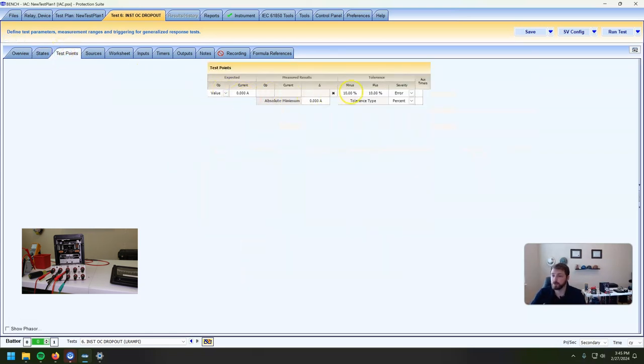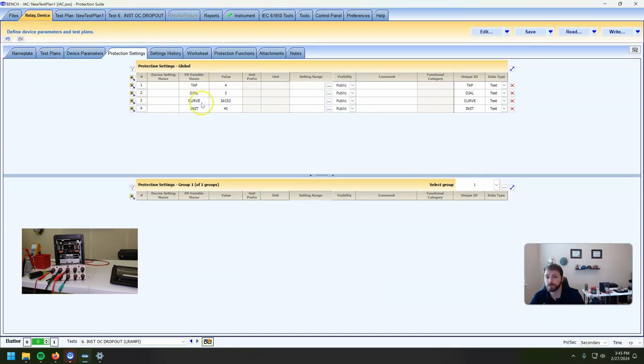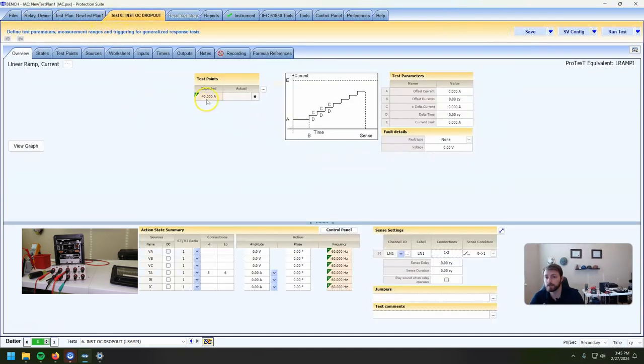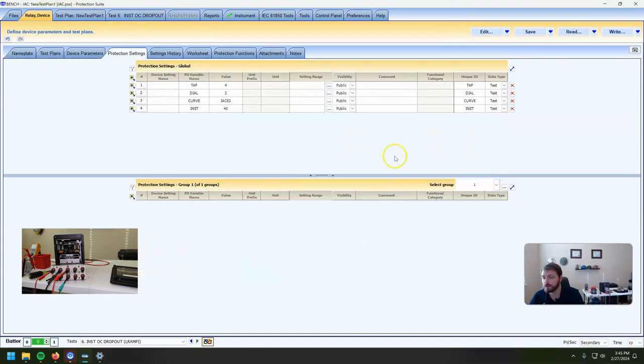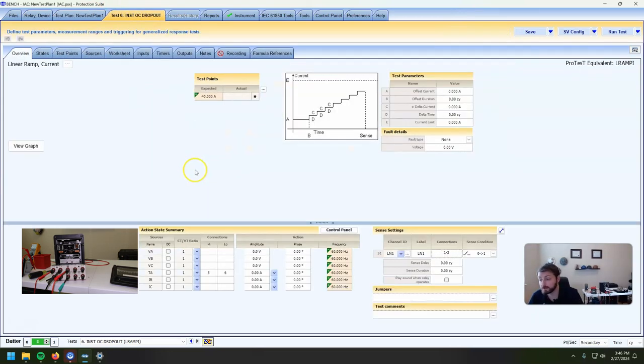The dropout should be roughly as accurate as the pickup. There's our 40 amps. The reason I take the extra step to put the settings in here and then reference the variable instead of just typing 40 amps: I can use this test plan over and over again, and all I have to do is change that one settings page. Then I come to my test plan, run all these in order, and everything just works great.